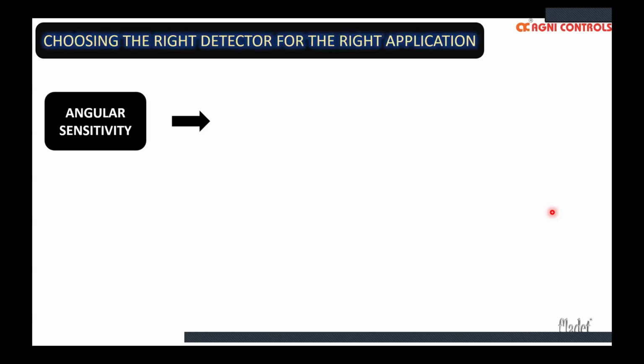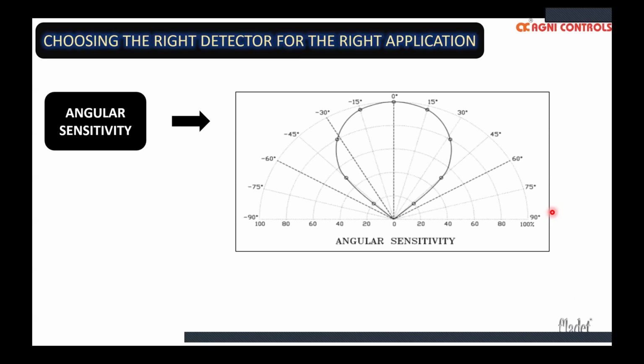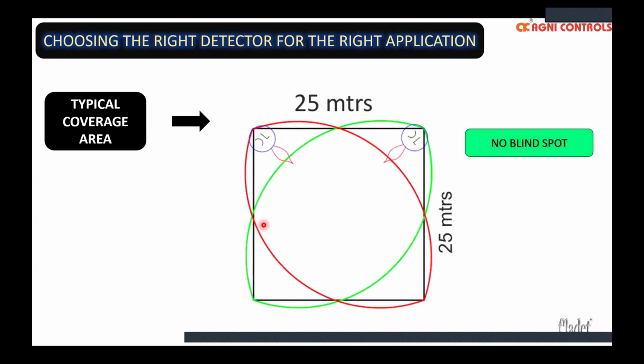So what should be taken into consideration is the angular sensitivity of the flame detector. The flame detector has a wide range of angular sensitivity, from 45 degrees left, right, up, and down, which basically forms a 90-degree cone of vision. A single detector along the optical axis, that is the center point, has a detection capability of more than 30 meters. And for a typical coverage area, just for reference, I've shown a 25 meter by 25 meter area, which is 625 square meters, that can be effectively covered by using just two flame detectors. But the only catch is that there should be no blind spot. This is similar to a human eye. If there is some object blocking your view, you cannot see what is behind it. Similarly, the flame detectors shall have no blind spots while positioning these detectors.